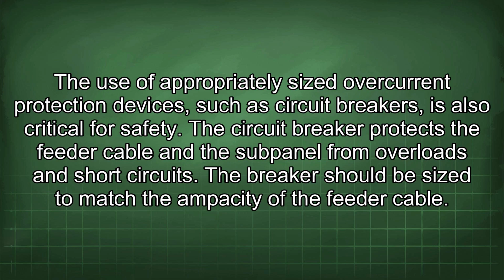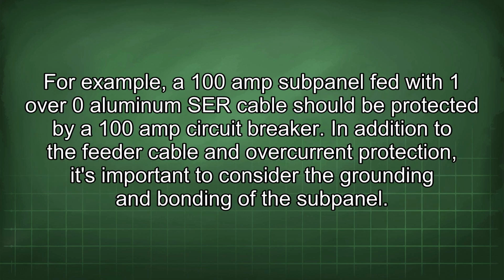The use of appropriately sized overcurrent protection devices, such as circuit breakers, is also critical for safety. The circuit breaker protects the feeder cable and the subpanel from overloads and short circuits. The breaker should be sized to match the ampacity of the feeder cable.